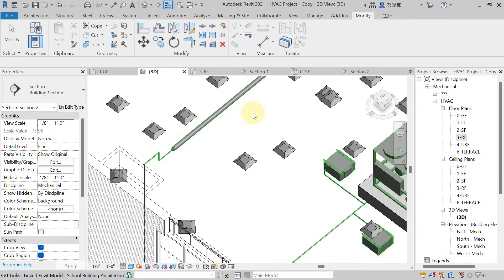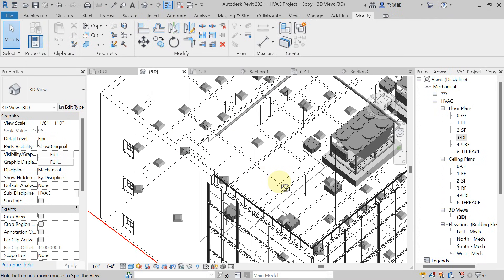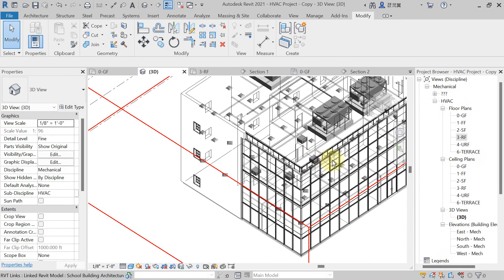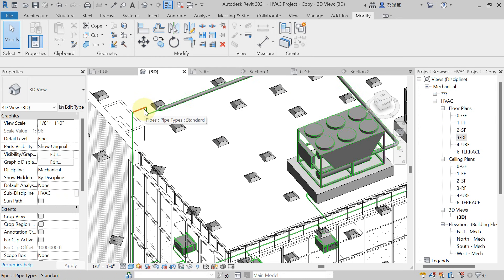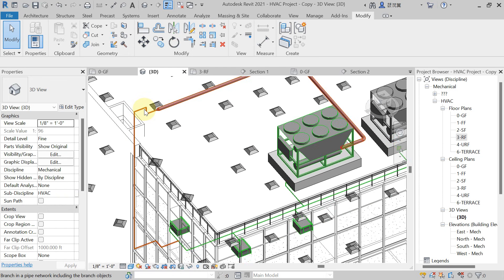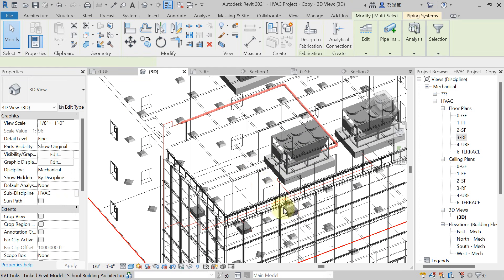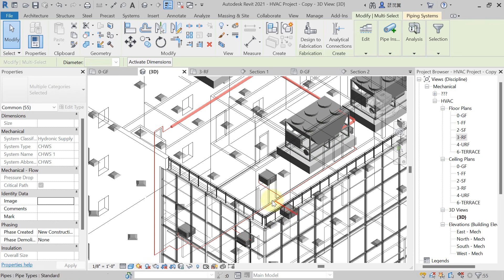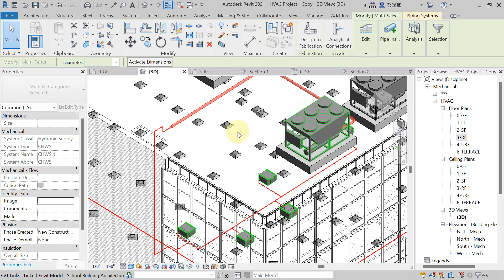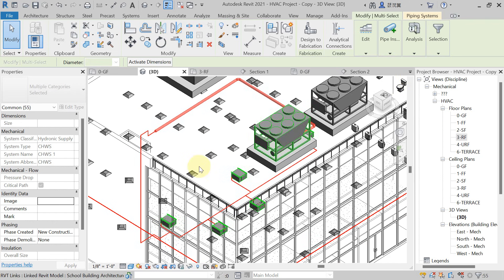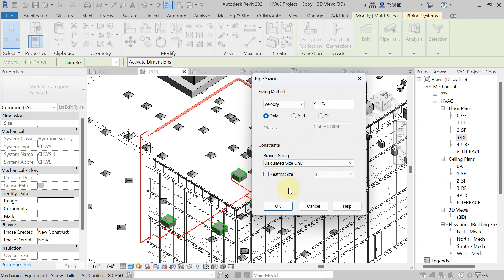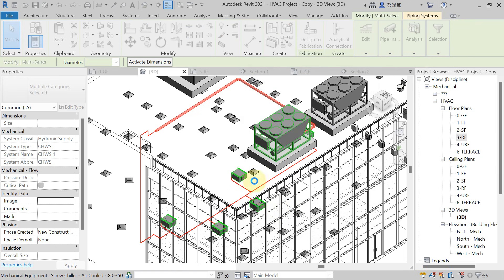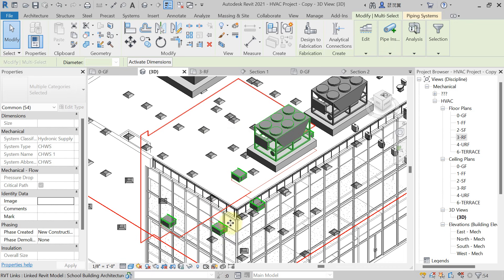Come here in 3D view. We have connected this to the chiller. Now for automatic piping sizing, take the mouse near to any pipe segment and press Tab to select the complete piping. The complete piping is selected. In the Analysis panel, hit on Duct/Pipe Sizing — 4 fps velocity — and now automatic pipe sizing will be done by Revit.